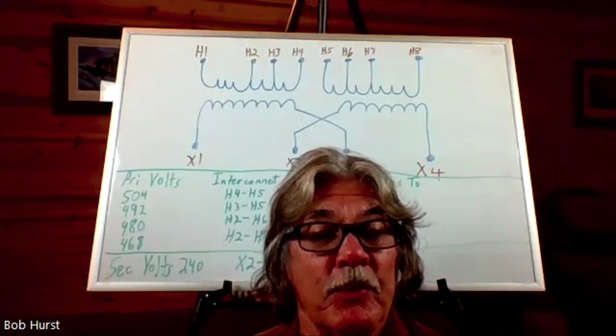The basic information on a transformer is it's a ratio of the windings of the primary versus the secondary. So if you've got a 4 to 1 winding, say 480 and 120, that's 4 to 1, because 4 times 120 equals 480. So you've got your primary and your secondary. I've got a drawing right here showing your primary volts and windings, and your secondary.